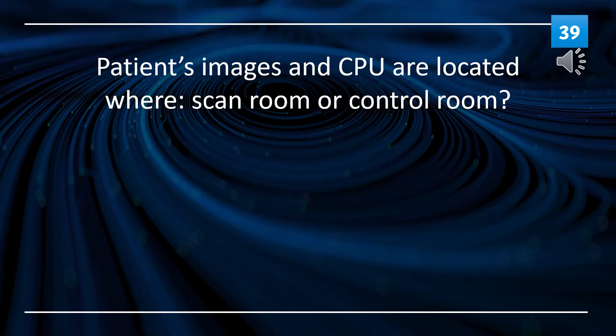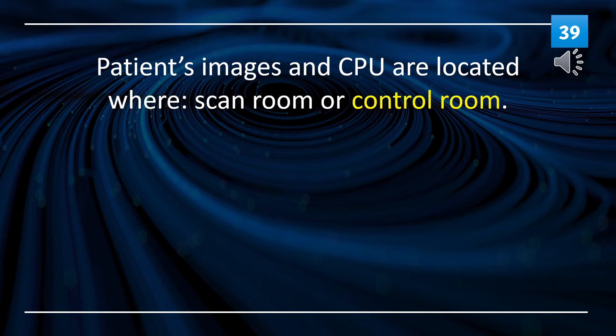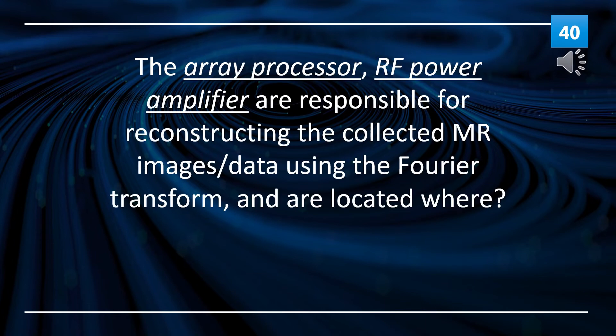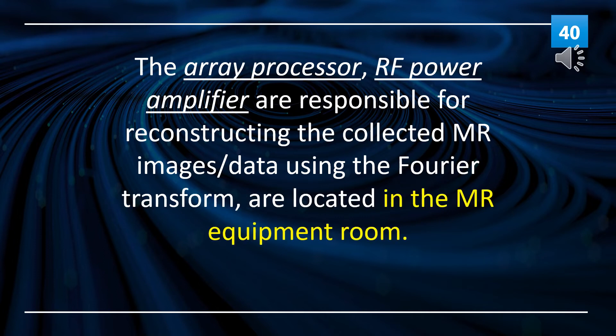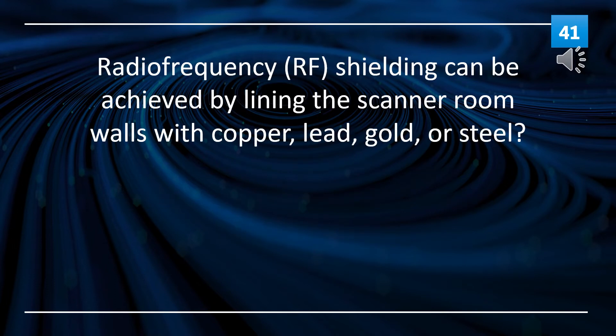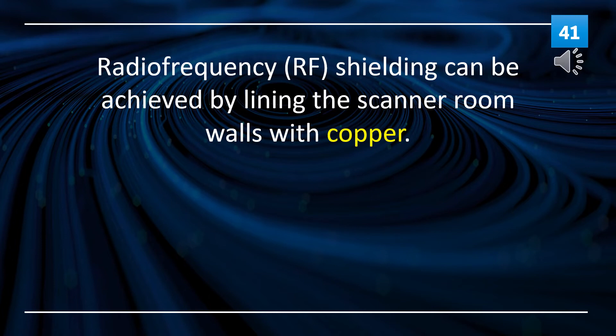The patient's images and CPU are located in the control room. The array processor and RF power amplifier are responsible for reconstructing the collected MR image data using the Fourier transform, and are located in the MRI equipment room. Radio frequency (RF) shielding can be achieved by lining the scanner room walls with copper.